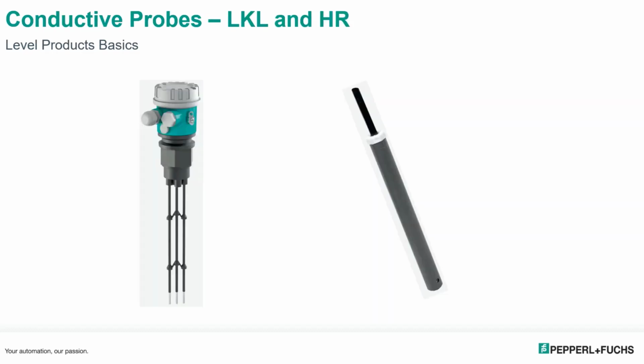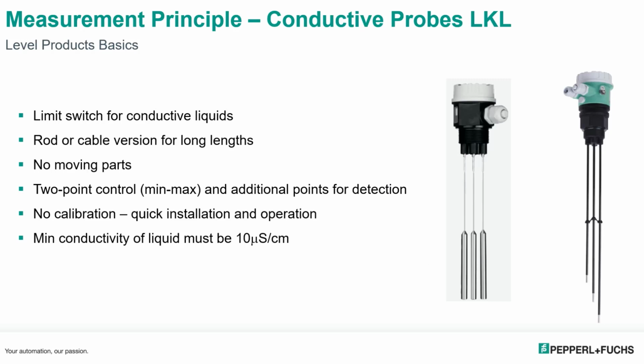Another point level control that we offer is the conductive probe, the LKL and the HR probes. The principle behind the conductive probes is they are for point level control, and they measure the conductivity of the liquid. If you're measuring the conductivity in air, it's very high resistance, as opposed to when the water reaches the 2 probes, it will activate the switch. These come in rod or cable versions, obviously the cable versions for longer lengths. There are no moving parts in them because it's all conductive. You can do 2-point control for min-max, and you can also add additional points for detection, up to about 5-point control in one housing. No calibration, and the minimum conductivity of the liquid must be at least 10 microsiemens per centimeter.